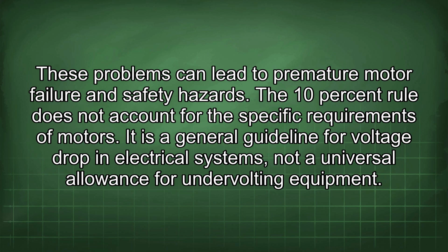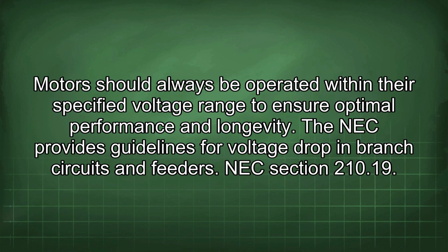The 10% rule does not account for the specific requirements of motors. It is a general guideline for voltage drop in electrical systems, not a universal allowance for undervolting equipment. Motors should always be operated within their specified voltage range to ensure optimal performance and longevity.